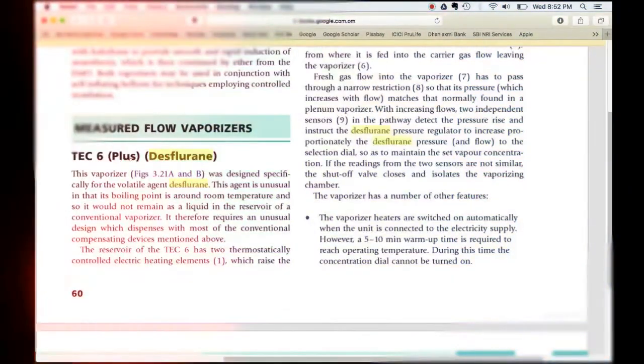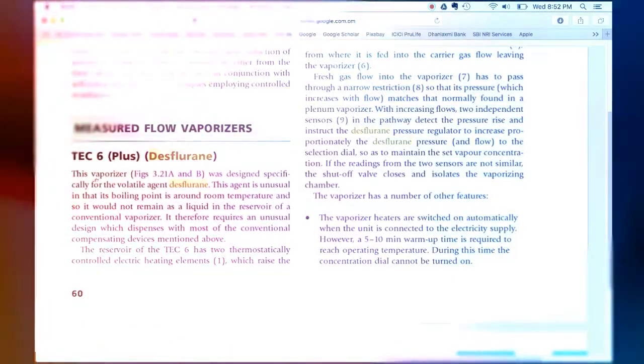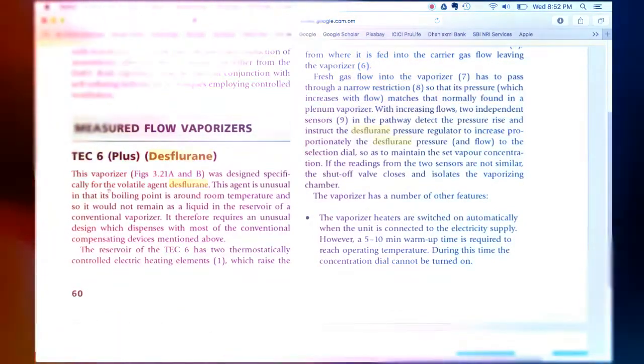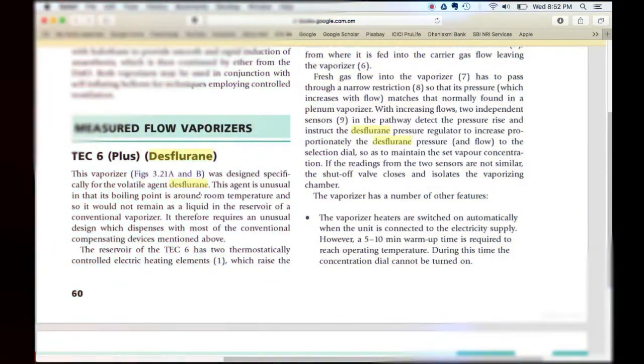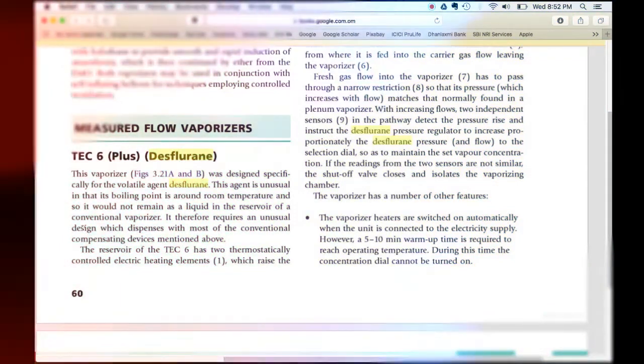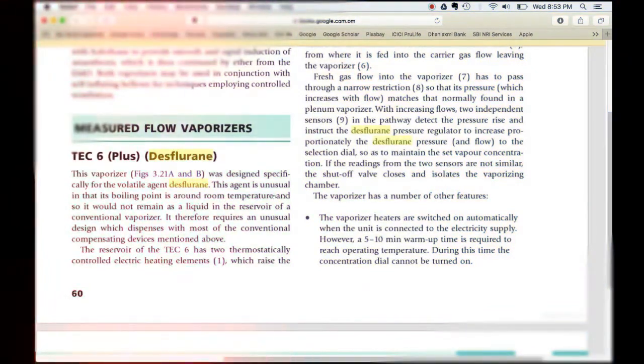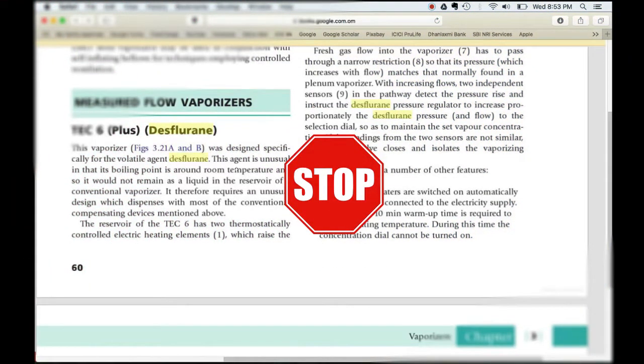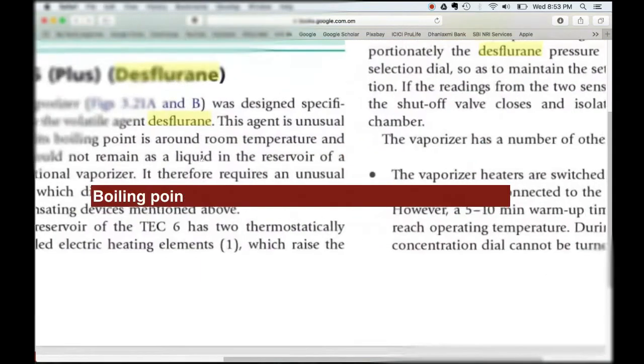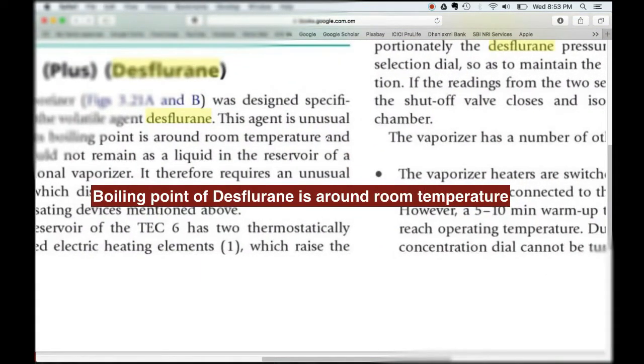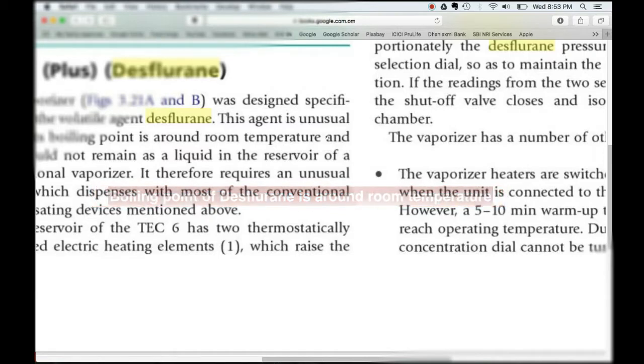TEC 6 Plus, this vaporizer was designed specifically for the volatile agent desflurane. This agent is unusual in that its boiling point is around room temperature. Yes, desflurane's boiling point is 22.8 degrees, which means it is an extremely volatile liquid inhalational agent.